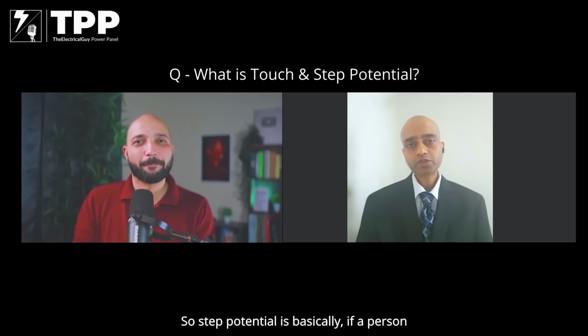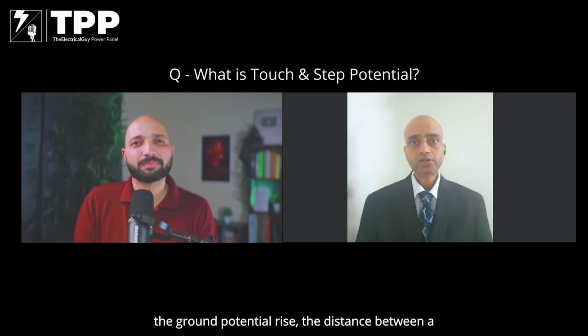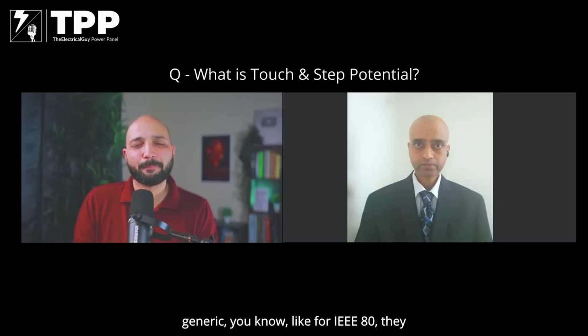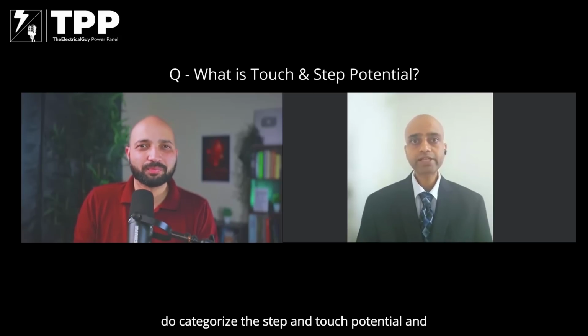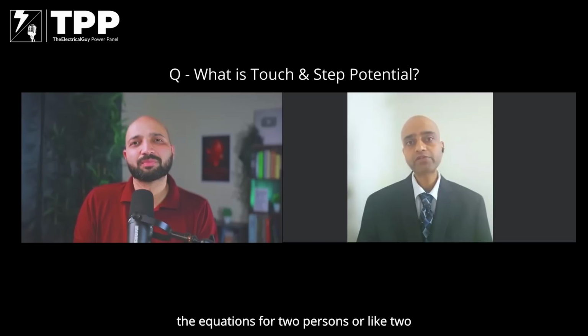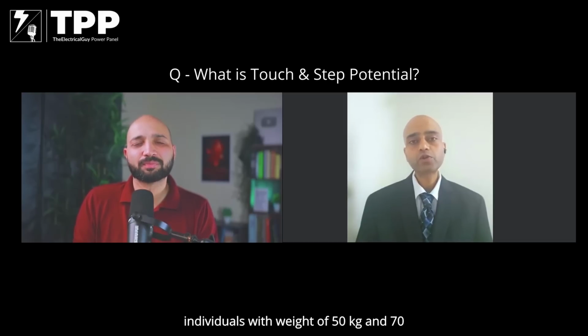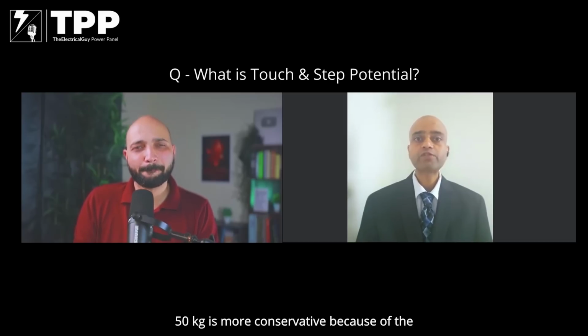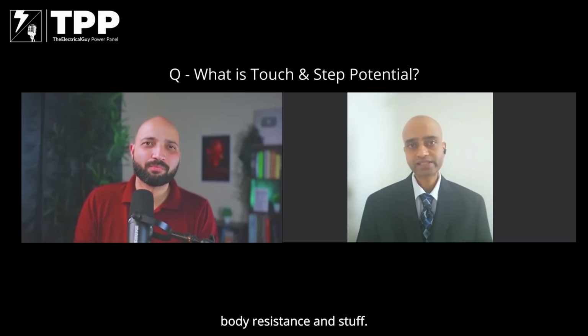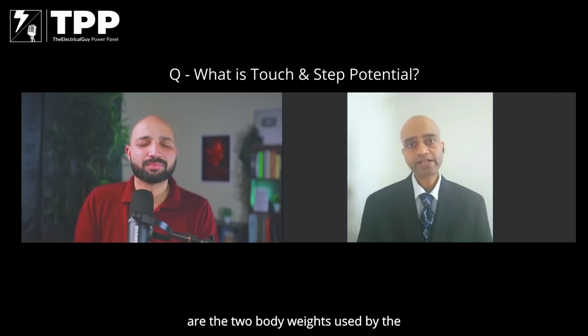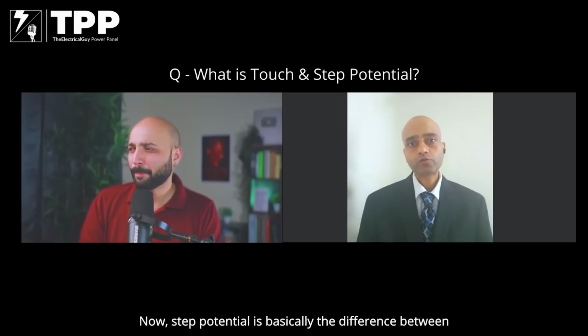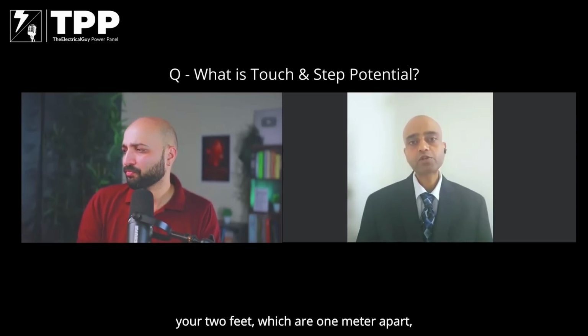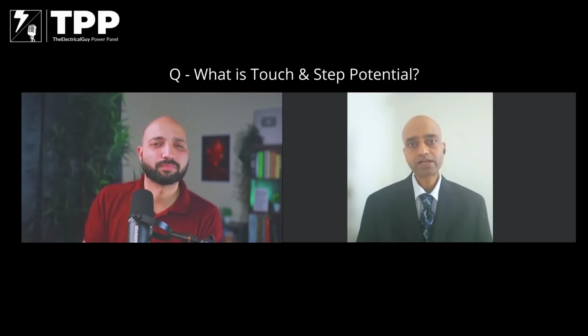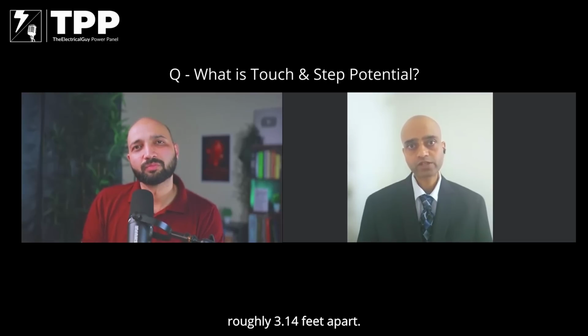Step potential is basically, if a person is approaching a substation which has ground potential rise, the distance between... for IEEE 80, they categorize the step and touch potential and the equations for two persons or individuals with weight of 50 kg and 70 kg. 50 kg is more conservative because of body resistance and such. Those are the two body weights used by IEEE. Now, step potential is basically the difference between your two feet, which are 1 meter apart, roughly 3.28 feet apart.